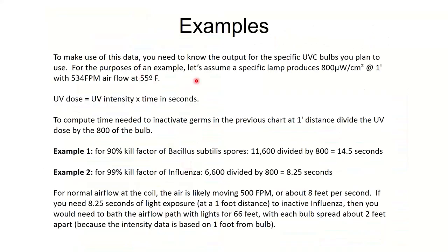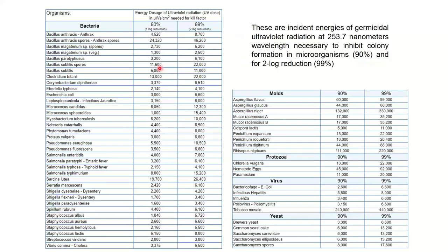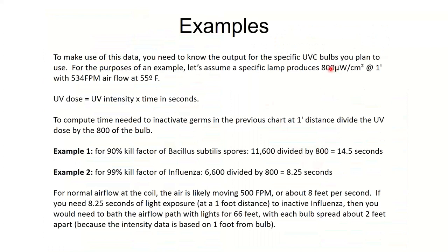So if I take an example here, I'm going to use a standard UV bulb, a fairly good UV bulb for that matter. Some of the residential ones are only around 600, but this one I chose was pretty good. 800 microwatts per centimeter squared at 1 foot away is what this bulb produces, per the manufacturer. I'm going to take a specific germ, in this case, Bacillus subtilis, I can't even pronounce it, and I want to kill 90% of it. So from the table I need 11,600. If I take that intensity bulb, 800, so divide 11,600 by 800, I need 14.5 seconds of shine time at a 1 foot distance in order to kill this.